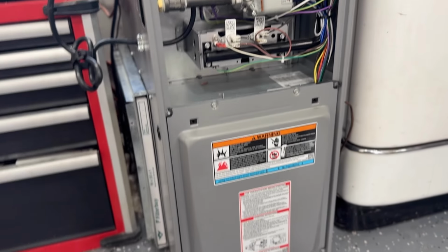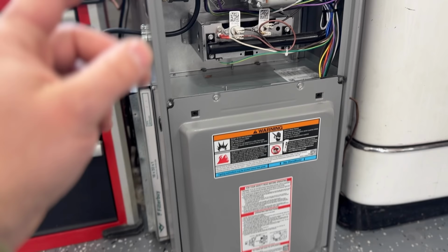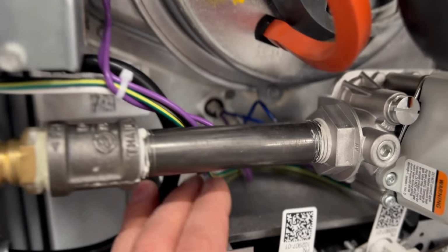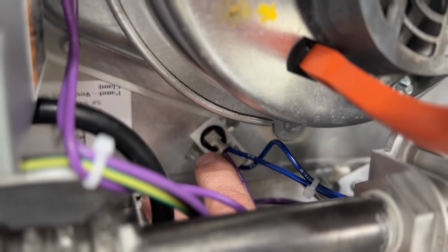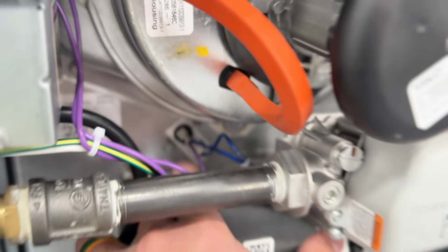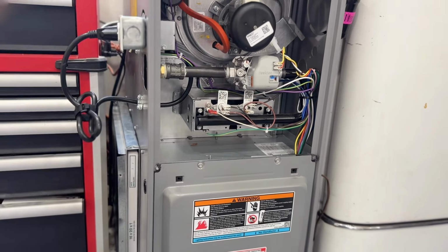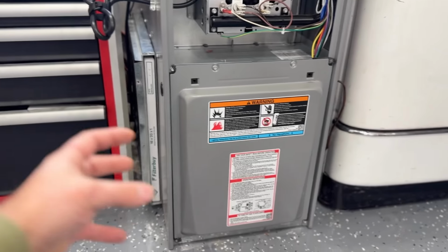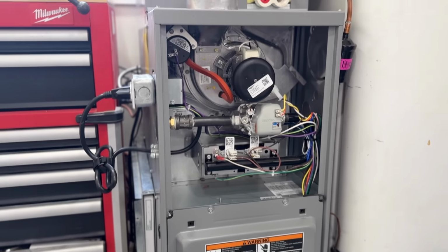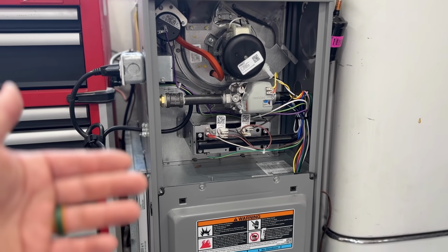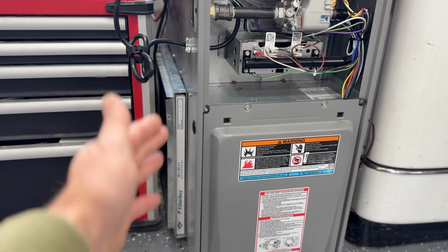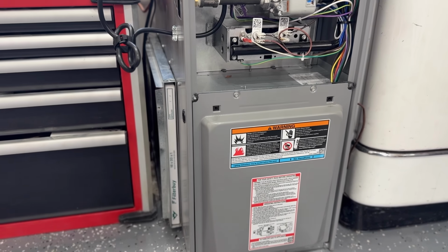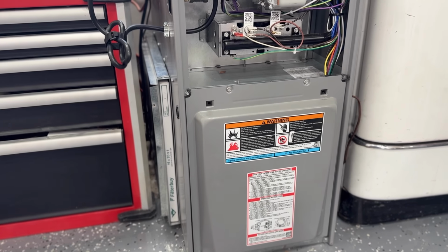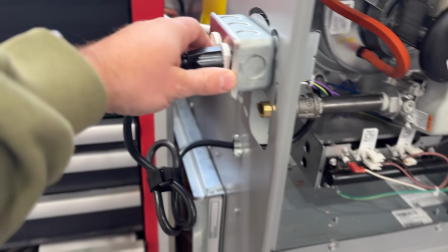And the reason behind that is if you're not getting enough air to go through here and through the heat exchanger, it's going to overheat, and there are sensors in here. In fact, this sensor right here on the firewall basically tells you if your system is overheating, it will turn everything down. You have to have enough airflow flowing through that heat exchanger in order for the furnace to keep running, and your filter is critical. So first of all, just make sure that your filter looks good. If it's dirty, replace the filter and reset the system.